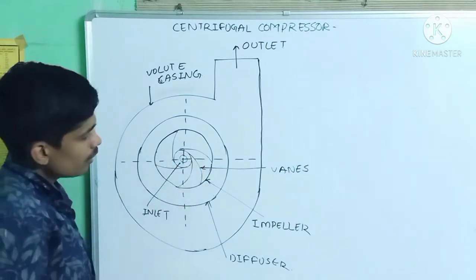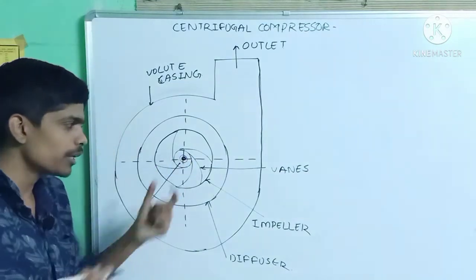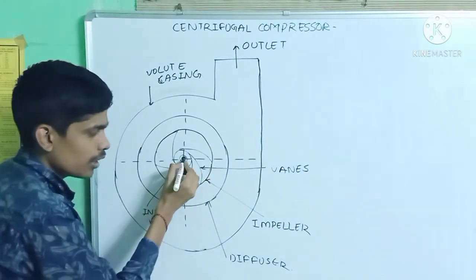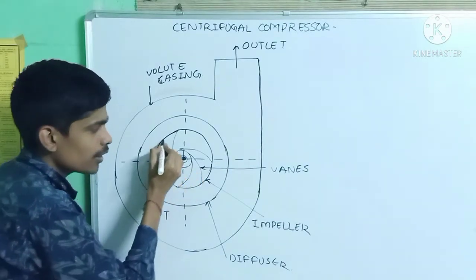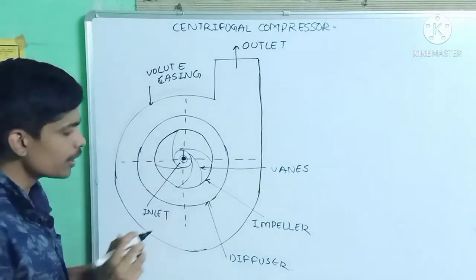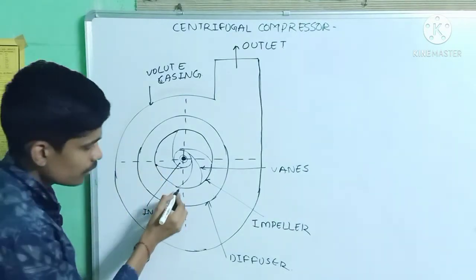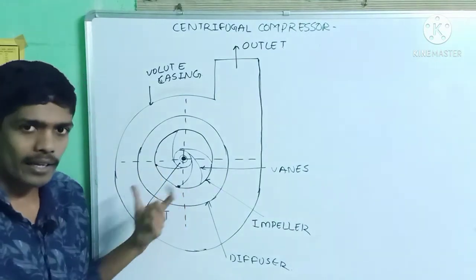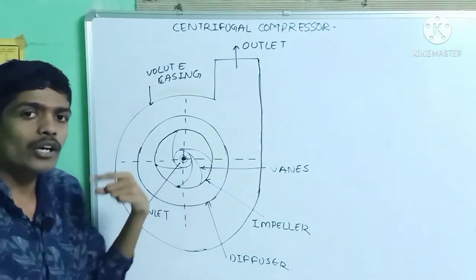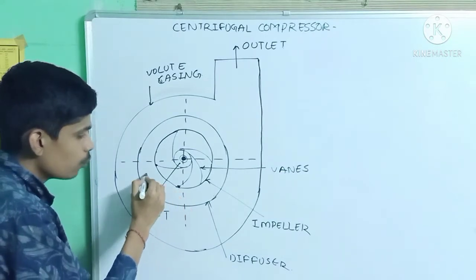When the impeller rotates, the vapor refrigerant from the inlet moves toward the periphery of the impeller and reaches the tip of the vanes. Here it attains kinetic energy. This kinetic energy is then converted into pressure energy as the vapor refrigerant moves through the diffuser.